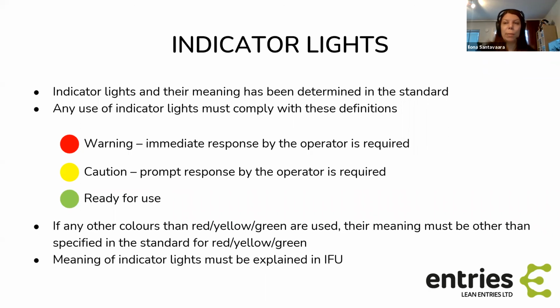So you cannot have, for example, a yellow light just indicating that something is on or something is being charged, for example. And if any other colors than red, yellow, or green are used, their meaning must be other than what is specified here for red, yellow, and green. So if you use a blue light, it cannot mean that it's ready for use or that it's a warning or caution. And then you also must explain the meaning of these lights in the instructions for use, even if you are using red, yellow, and green according to this instruction. So it must be made sure that the user is aware as well.